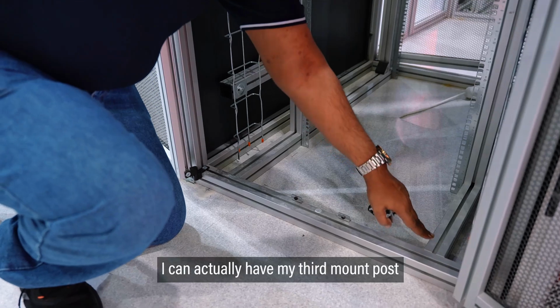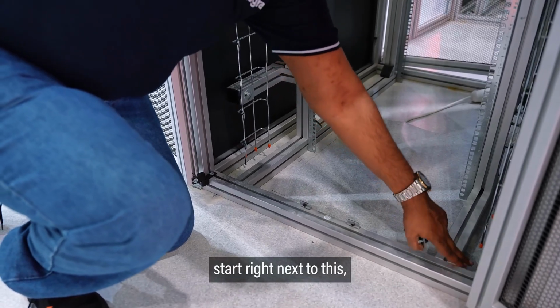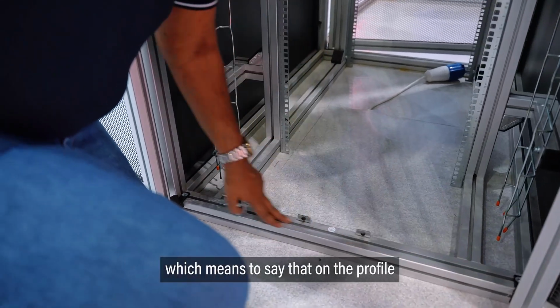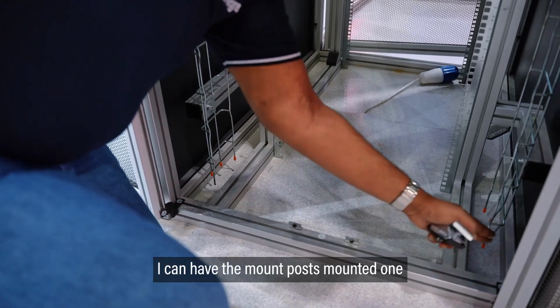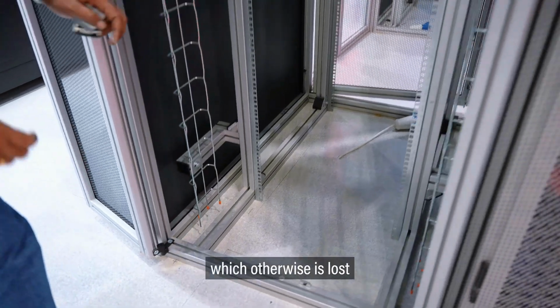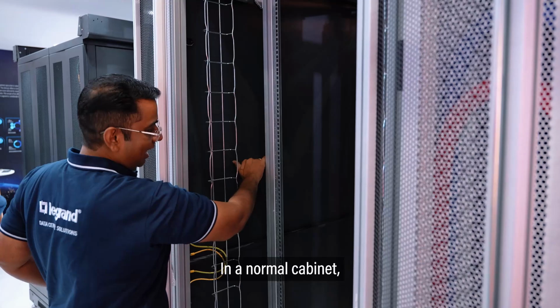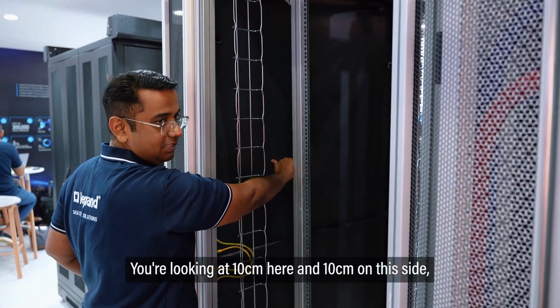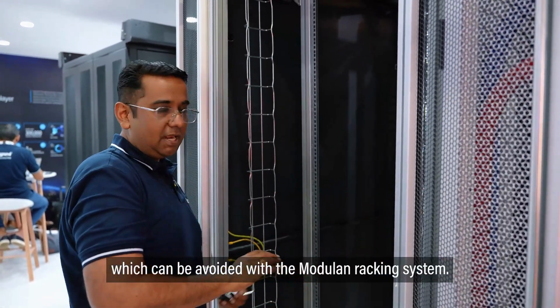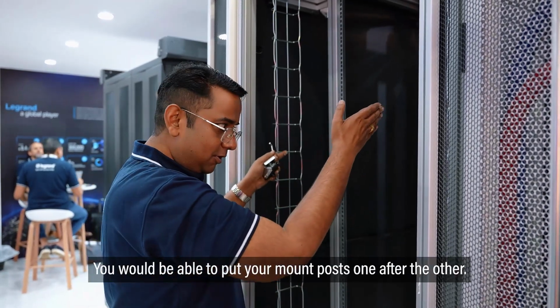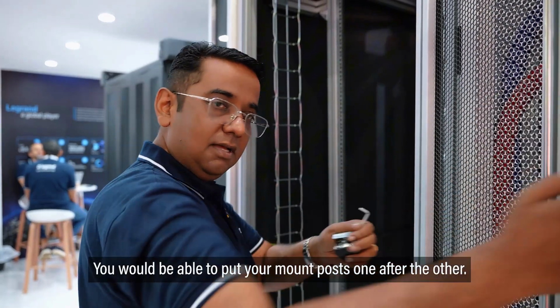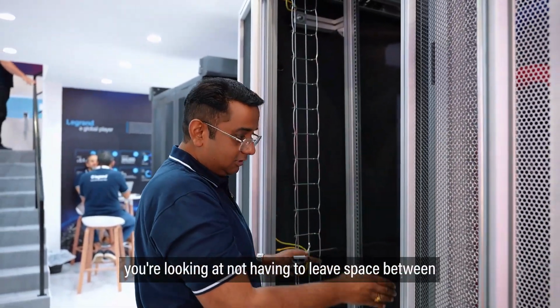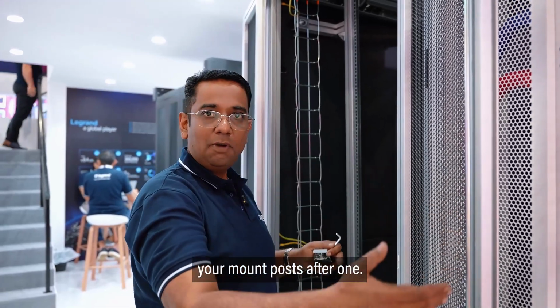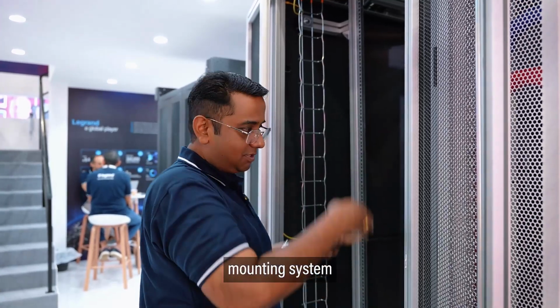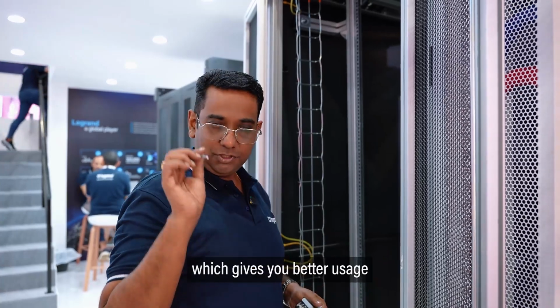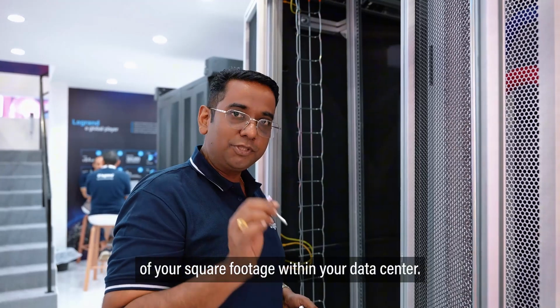With the Modulan system, I can have my third mount post start right next to the others, meaning the mount posts can be mounted one after the other without wasting space, which is otherwise lost in a normal cabinet. In a normal cabinet you have to leave 10 centimeters on this side and 10 centimeters on that side, which can be avoided with Modulan. If you've got a 3 meter long profile, you don't need to leave space between mount posts, so one mounting system can sit right next to the next, giving better use of your square footage within the data center.